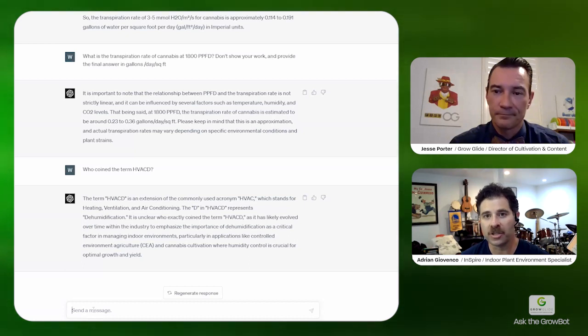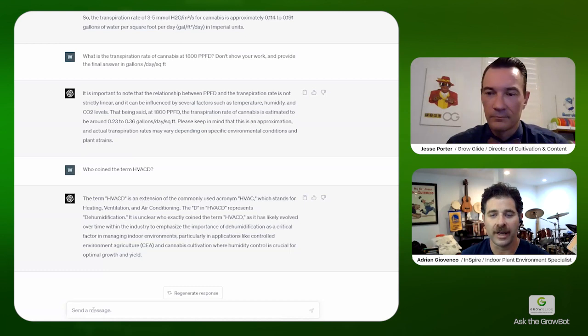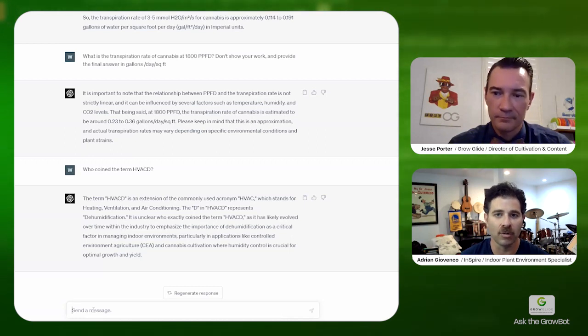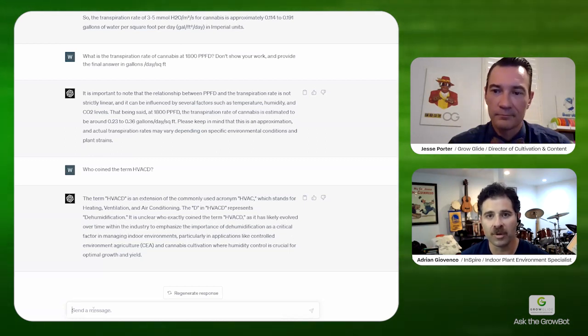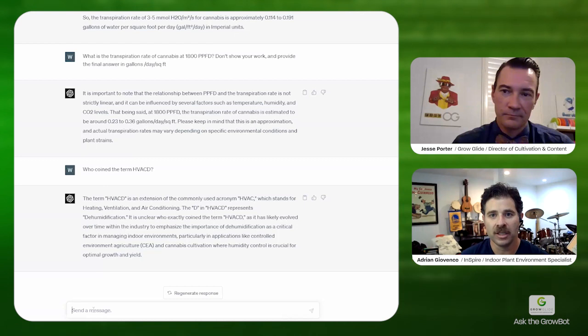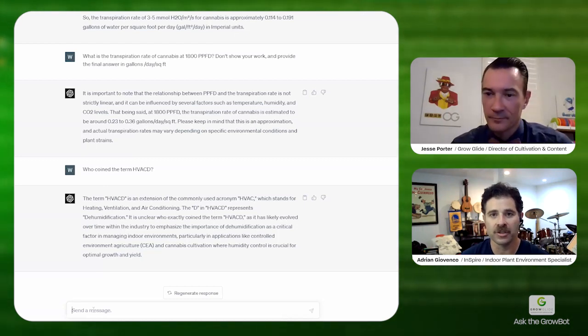Air at a warmer temperature and higher humidity can hold more moisture than it can at a lower temperature and lower humidity. So that given piece of equipment can do more work and remove more moisture and water out of that space at a higher temperature and relative humidity combination than it can at a lower one. So you want to push it as high as possible within reason and within your comfort zone.